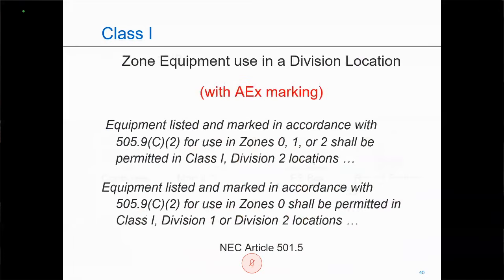Now, there are times that you may come across zone-rated equipment. Zone-rated equipment is the IEC parallel for division classifications. And we do allow for zone-rated equipment under Article 505 for gases and vapors and Article 506 for combustible dust. And there are times that zone-rated equipment may be used in Division areas. So if I have an area rated Zone 0, Zone 1, or Zone 2, I may use that equipment in a Class 1 Division 2 area, provided it's approved for the proper gas group and any applicable temperature ratings as necessary. And product that is approved for Zone 0 may be used in a Class 1 Division 1 or Class 1 Division 2 area, providing I have the AEx marking.